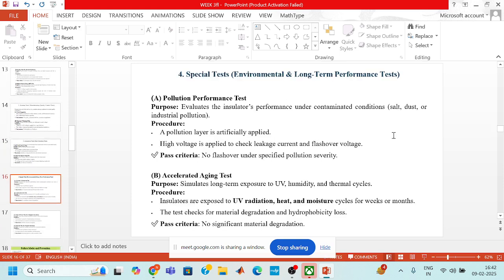Now last is the special test. A special test is for environmental and long-term performance, and in this there are categories like the pollution performance test. It evaluates the insulator's performance under contaminated conditions such as salt, dust, or industrial pollution. The procedure is that a pollution layer is artificially applied to the insulators, and a high voltage is applied to check leakage current and flashover voltage.